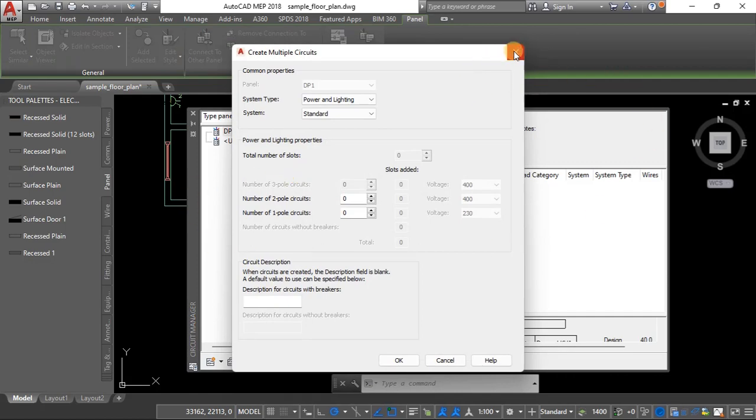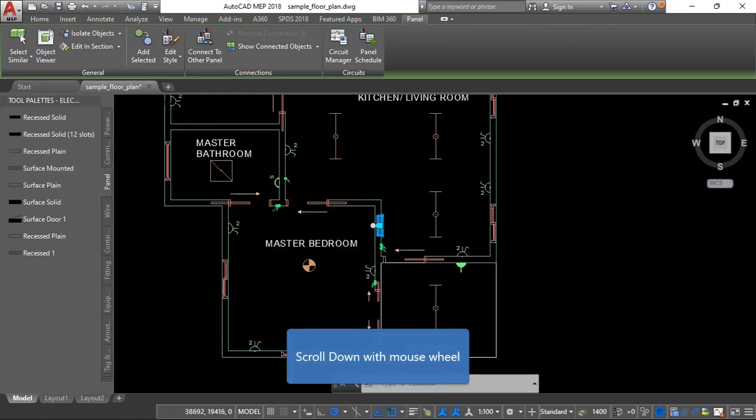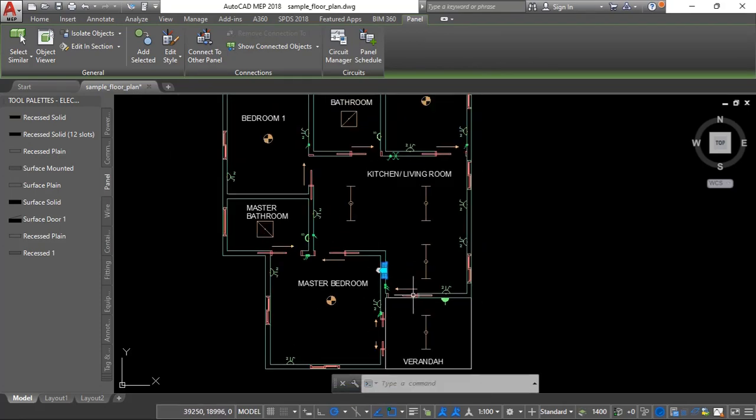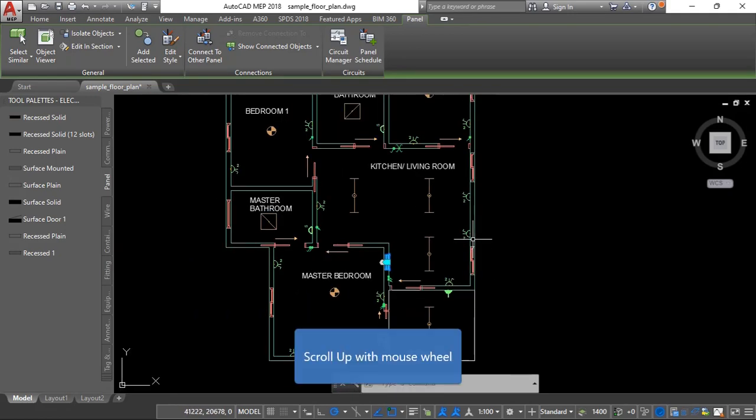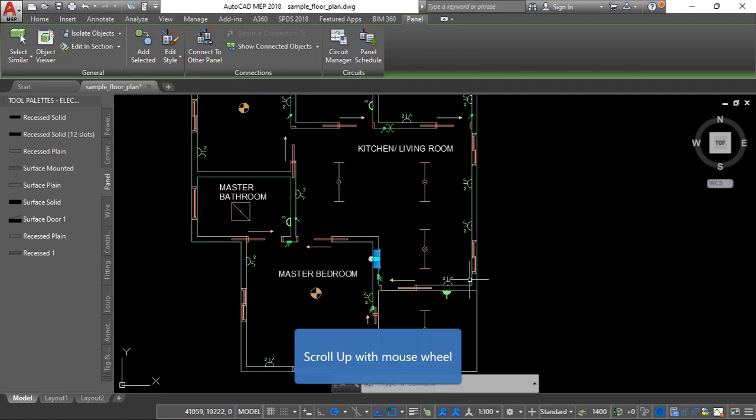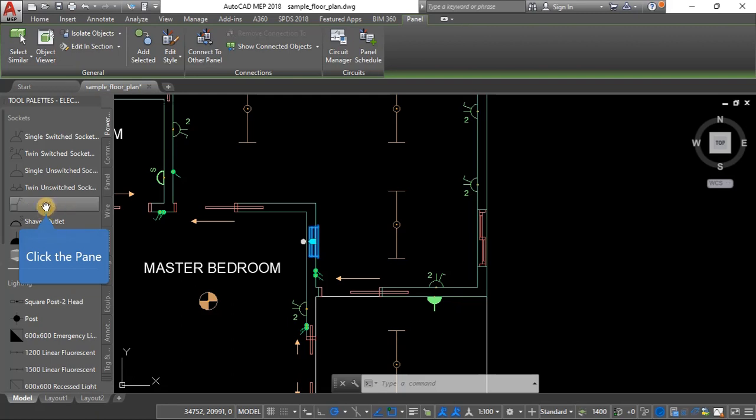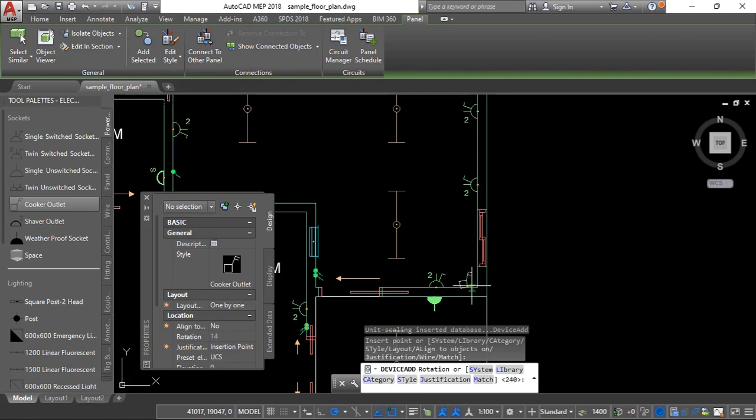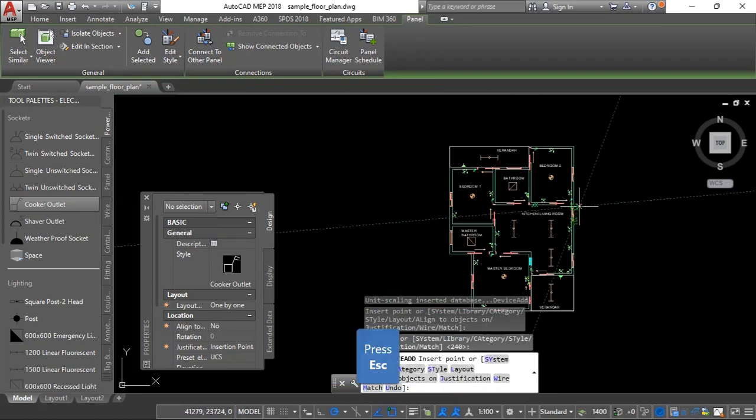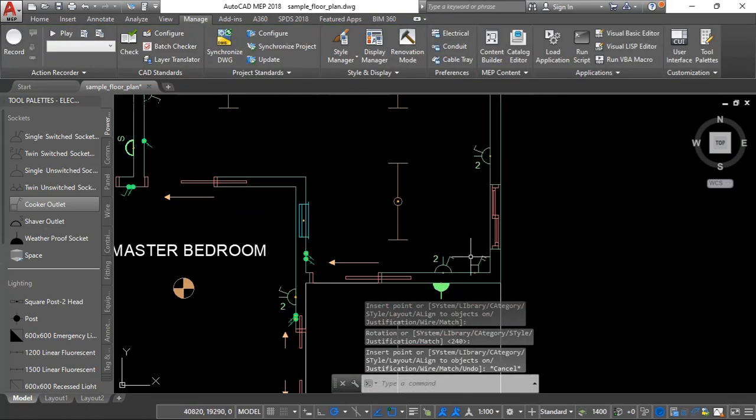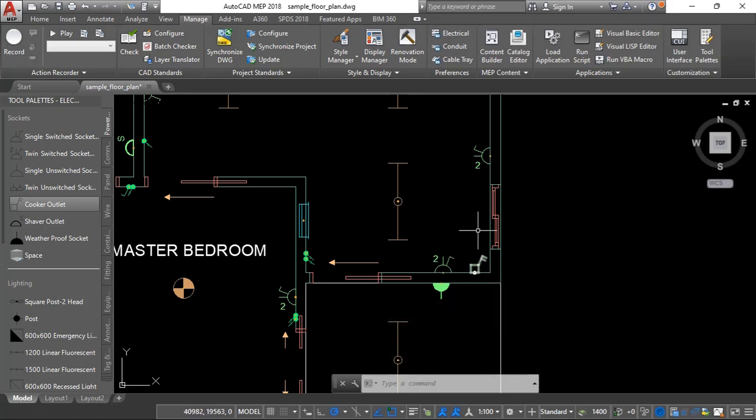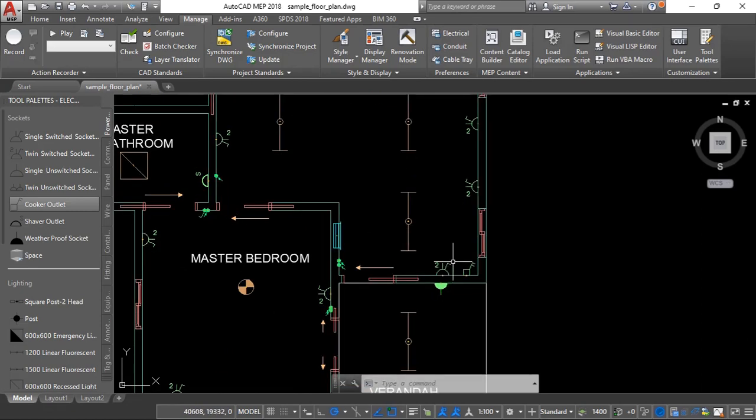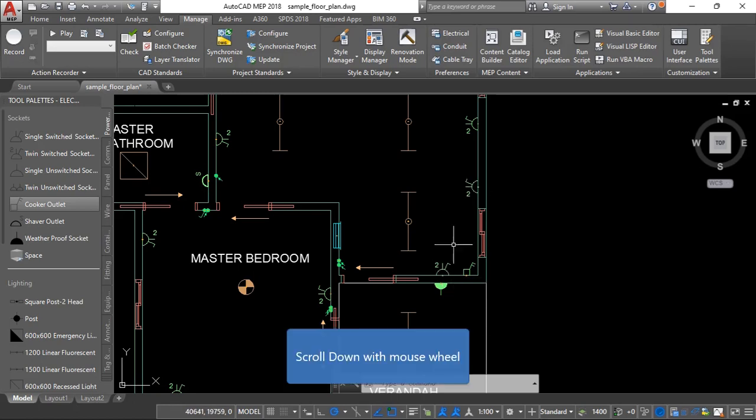Yeah so before we actually get to creating circuits we need to identify how many circuits we need in this house. So usually we need, actually there's a missing item here, we're missing a cooker control unit. So yeah there's a cooker control unit missing. Okay so I think it's best we put it here. Yeah that was the only thing missing. So we need to create a circuit for this cooker control unit, a single circuit for 32 amps. Then suppose we have a fridge and blender, we should give it a separate circuit. Okay, okay so what I'm going to do is maybe these two, this one and this one, I'll give them a separate circuit.